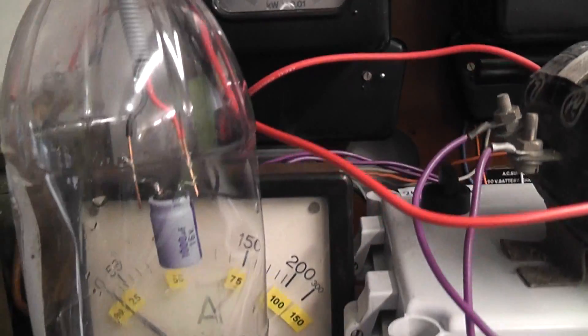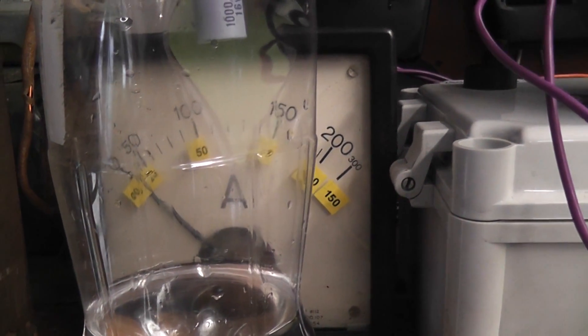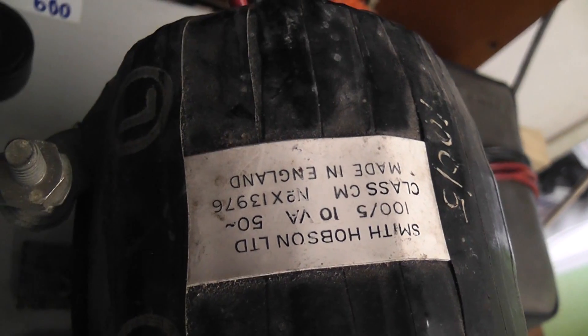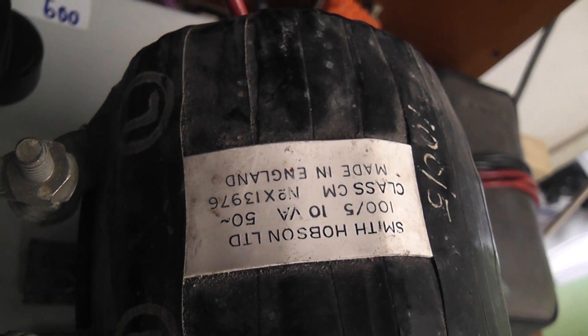The purple wire goes from the current transformer to the ammeter sits at the back here, and the ammeter, the yellow scale, is set up for 100 to 5 amps in this particular case. Current transformer is metering CT 100 to 5 amps.